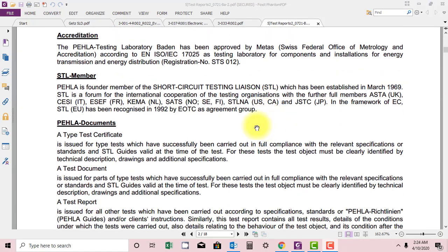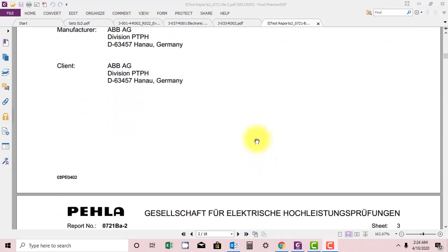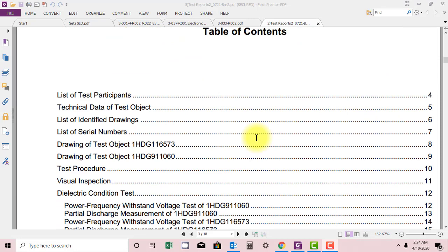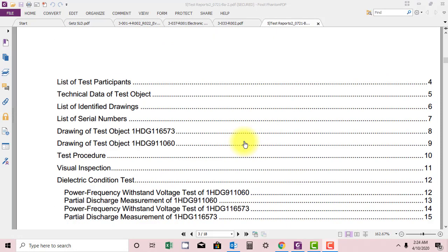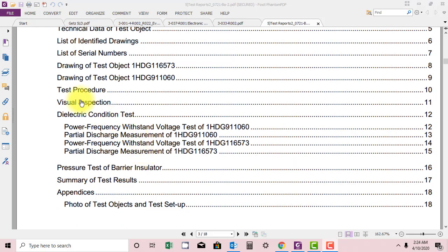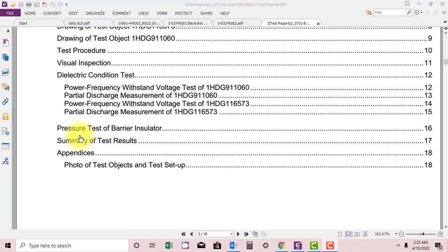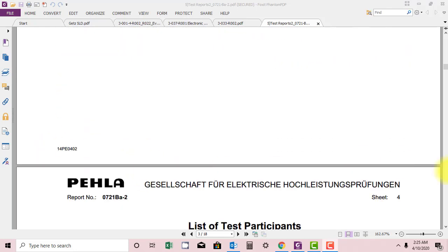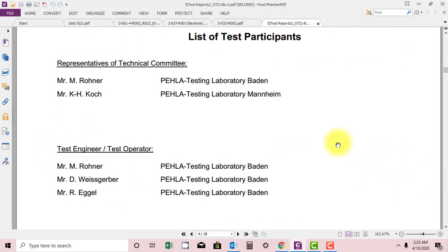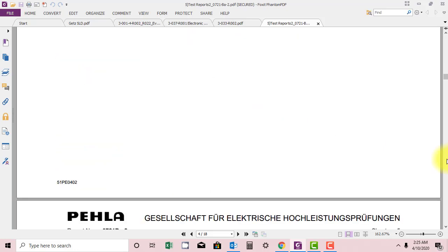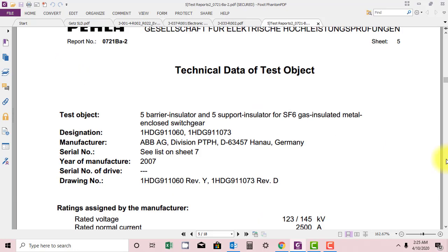This is the formality. I will also provide this in the source. List of participants, then they are attaching the drawings, test procedure is attached. Visual inspection, they will do the following tests: dielectric condition test, power frequency withstand voltage, partial discharge measurement, pressure test of barrier insulator. Summary of test results and then many pictures. Let's move on to the technical data of the test object.